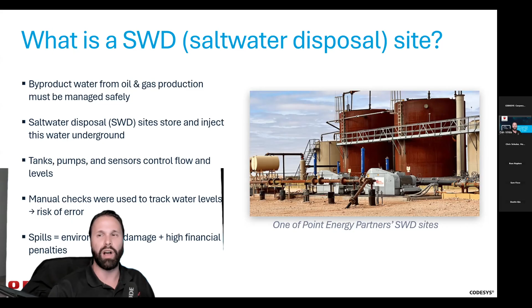Here's the situation they were dealing with at Point Energy Partners. The existing tank levels were being monitored by old hydrostatic head switches, meaning moving parts with floats that would tell you how high the fluid was. Over time, especially with water that's so caustic, those sensors would start to fail, becoming unreliable. That meant operators had to go on site and check tanks manually, leading to inconsistent data and, in a lot of cases, no way to know what was happening until you were physically on site.